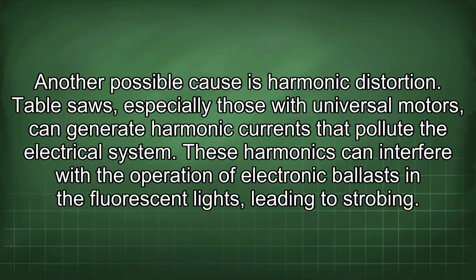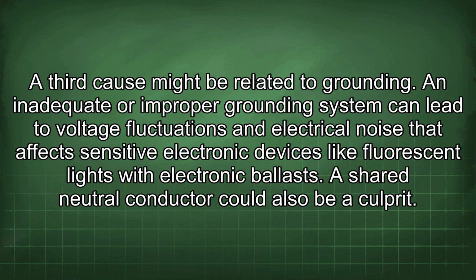Another possible cause is harmonic distortion. Table saws, especially those with universal motors, can generate harmonic currents that pollute the electrical system. These harmonics can interfere with the operation of electronic ballasts in the fluorescent lights, leading to strobing. A third cause might be related to grounding. An inadequate or improper grounding system can lead to voltage fluctuations and electrical noise that affects sensitive electronic devices like fluorescent lights with electronic ballasts.